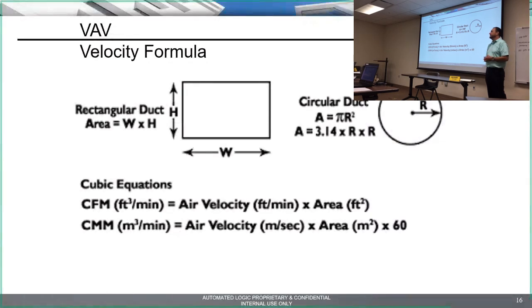We messed with it and couldn't figure out what the deal was. We had the mechanical contractor separate the flex from the VAV box, and it was a pair of pants. How a pair of pants got in a duct and flew all the way down and got up against that velocity pressure probe, who knows? I can't tell you. But that was the problem, and we weren't reading the correct velocity pressure for what air was coming out of the unit. Those kinds of things. So far, I know I'm flying through this, did that make sense? Everybody following me? Yeah, please stop me if you want to go into more detail.